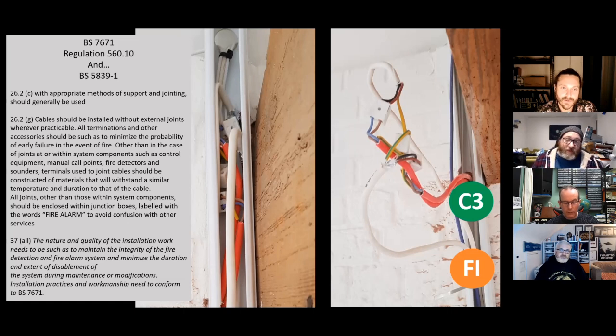The problem you have with marquees is everything has to look clean. So they'll put the steel structure in, put the canopies in, then throw sheets of material over to make it all blank canvas, then throw carpet in, and store the carpet in the corner, then bring cooking appliances in, and then be using hot works. Then their risk assessment will be to put a CO2 extinguisher and a foam extinguisher in the corner, which they'll then block off. It's an area I am bouncing backwards and forwards with fire risk assessors in the event industry.